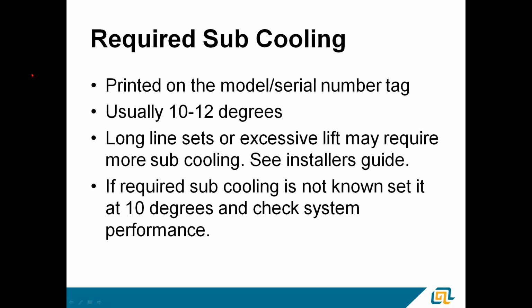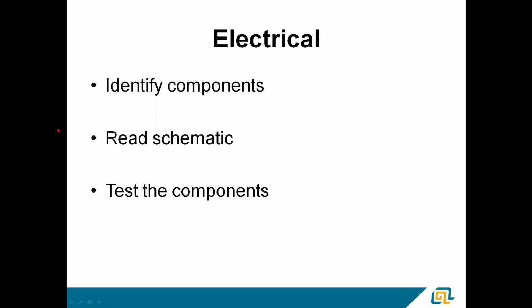If you're working on an older system, you happen to know it's got a TXV in there, and you just don't know what that subcooling should be, the best you can do is set it at 10 degrees and check system performance. 10 degrees of subcooling will probably get you there. Only, like I say, if you've got something that's excessively long line set or a lot of lift or something like that, that 10 degrees may not work. But for the most part, in our general installations and basements and stuff, 10 degrees of subcooling would be plenty.